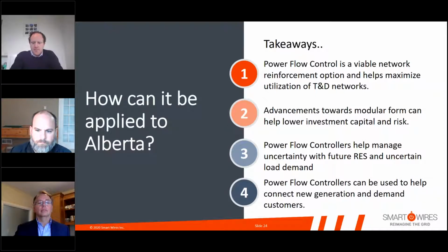And it can even be installed as an interim solution to longer term new line or reconductor projects. Flow controllers can help manage uncertainty with future renewables and uncertain load demand. So where justification of investments becomes difficult, a modular flow controller can help manage that and get you through 5 to 10 years until you build out bigger solutions. Finally, they can be used on the interconnection side as well, to help connect new generation or demand customers where capacity may be constrained.